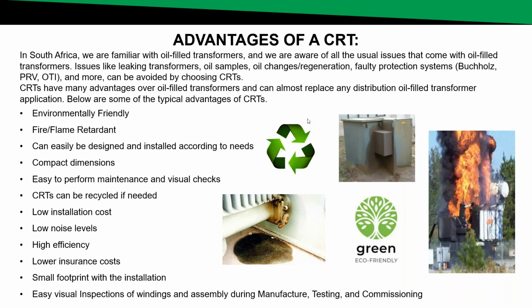So let's quickly discuss some of the advantages of cast resin transformers over oil-filled transformers. As I mentioned, cast resin transformers do not have any oil in them. No oil means no leaks. No oil also means lower risk of fire, and also no environmental impact should the oil leak.